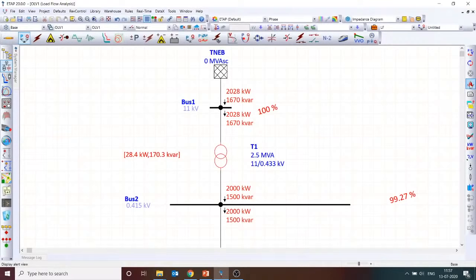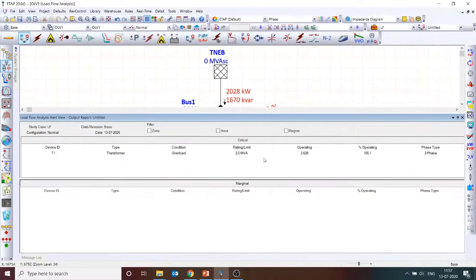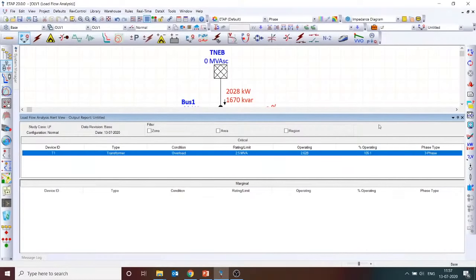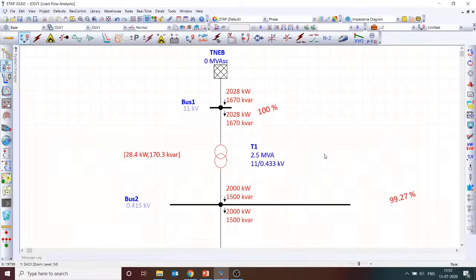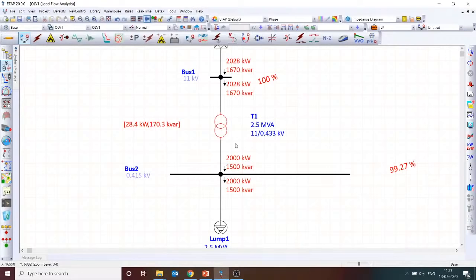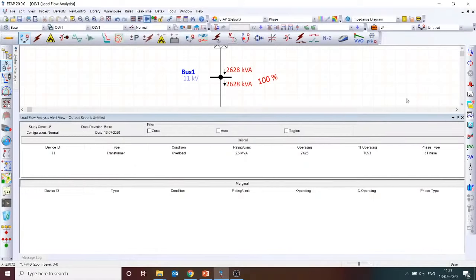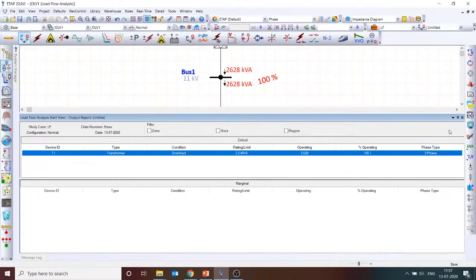How can I say that it is overloaded? You can see it in the alert view, which shows by what percentage the transformer is overloaded. So the transformer is 105% loaded. But I have connected a 2.5 MVA transformer with only a 2.5 MVA load, so how is it 105% loaded? Because of the losses in the transformer. On the LV side it is 2.5 MVA, but on the HV side it is 2.628 MVA. If you divide 2628 by 2500, you will get that 105%, which you can see here. That's perfect.